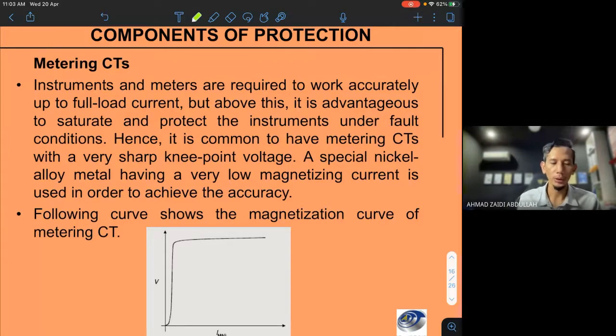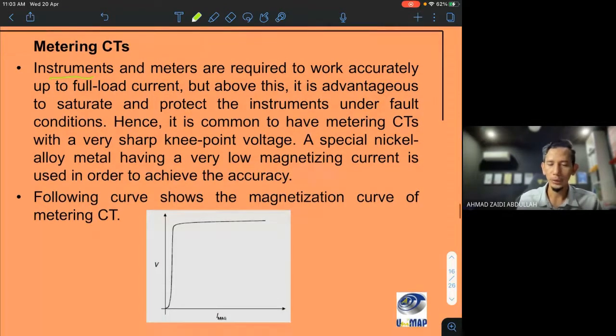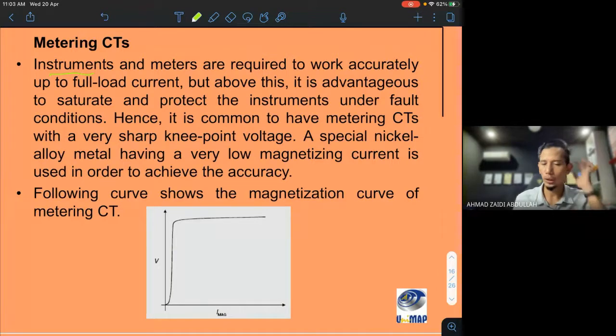Okay, metering CT, instrument and meter are required to work accurately up to full load current. But above this, it is advantageous to saturate and protect the instrument under fault condition. So let's say you have an ammeter, ammeter. So you have 0 to 100 amp. So the CT must have a level also of the metering to cover the full load.